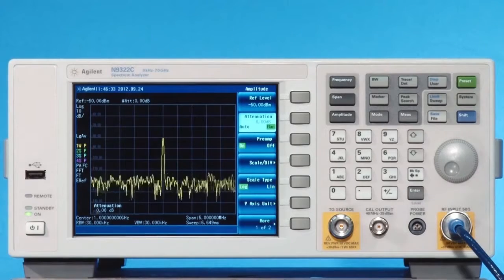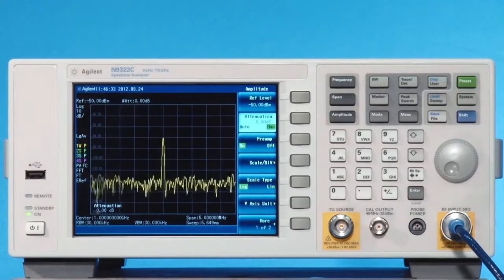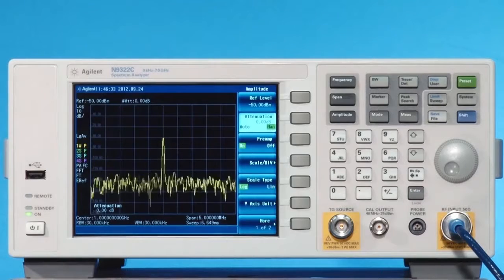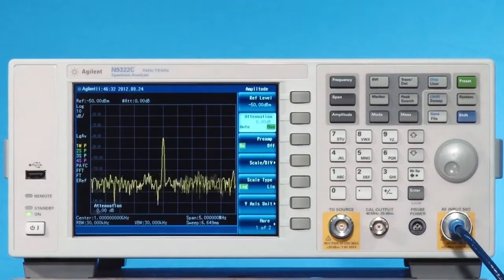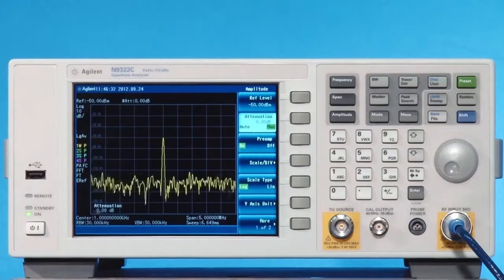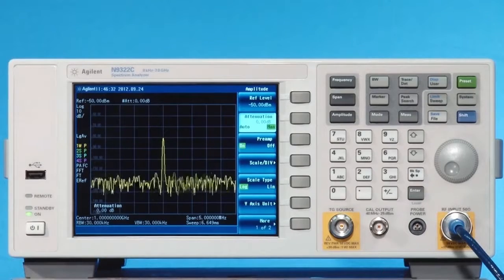To further reduce the noise level of the analyzer, you can narrow the resolution bandwidth, RBW. The RBW settings affect the level of internal noise without affecting the amplitude level of the input signal.